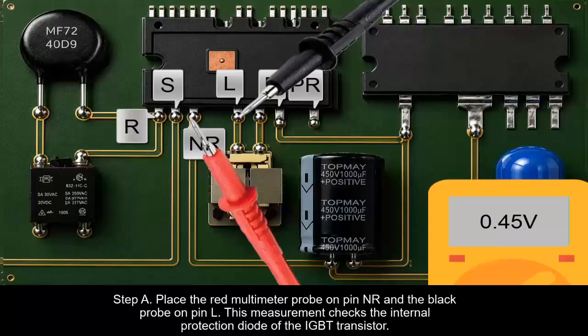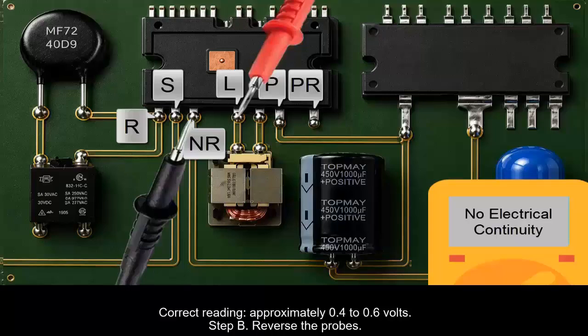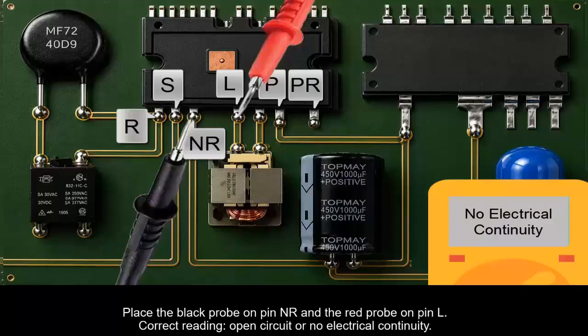Step B. Reverse the probes by placing the black probe on pin NR and the red probe on pin L. Correct reading: the multimeter should indicate an open circuit or no electrical continuity. If any of the measurements described above indicate a short circuit, continuity in both directions, infinite resistance where conduction should exist, or values significantly different from those indicated, it is highly likely that the PFC module is defective and requires further evaluation or replacement.